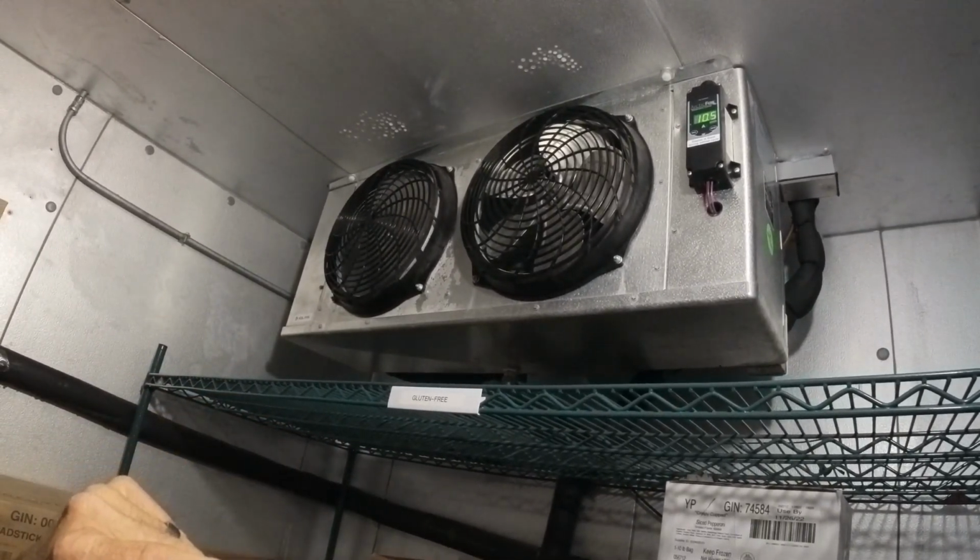All right, so that was unexpected. All the refrigeration guys were tied up, so one of the guys went there last night, filled it up, and got there today dry. So I had to find a leak, because if I just charged it, it wouldn't have lasted. It was short. So yeah, that was kind of an adventure.